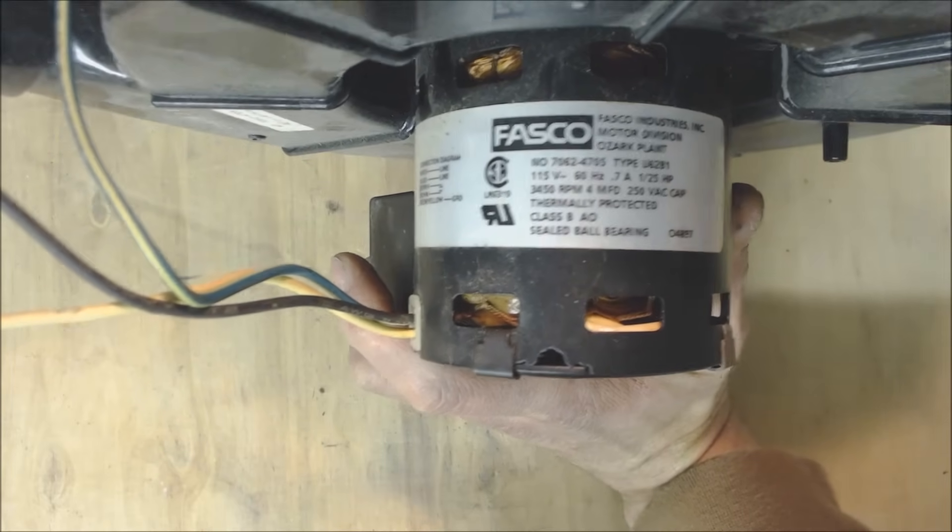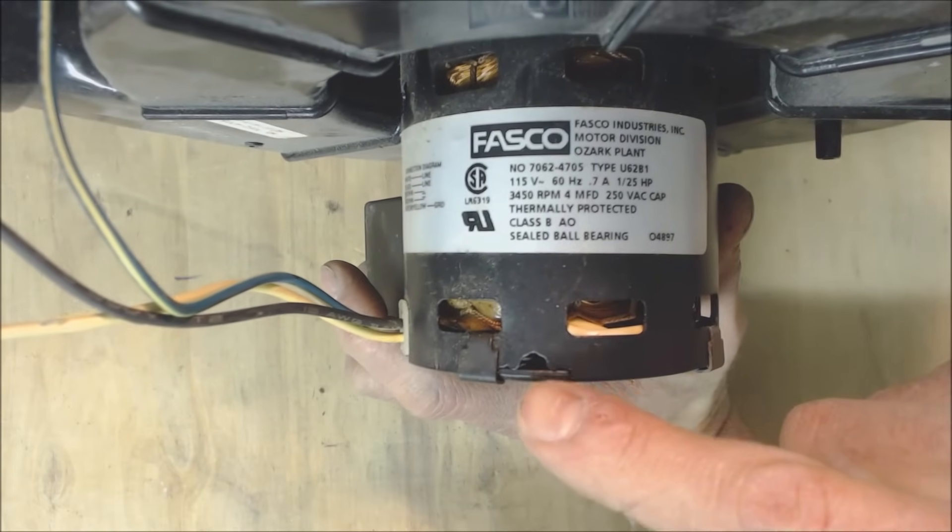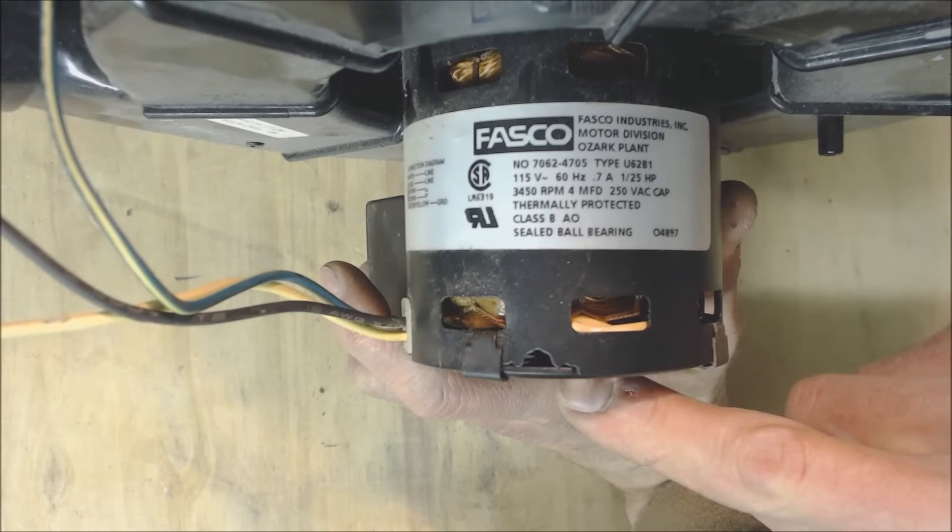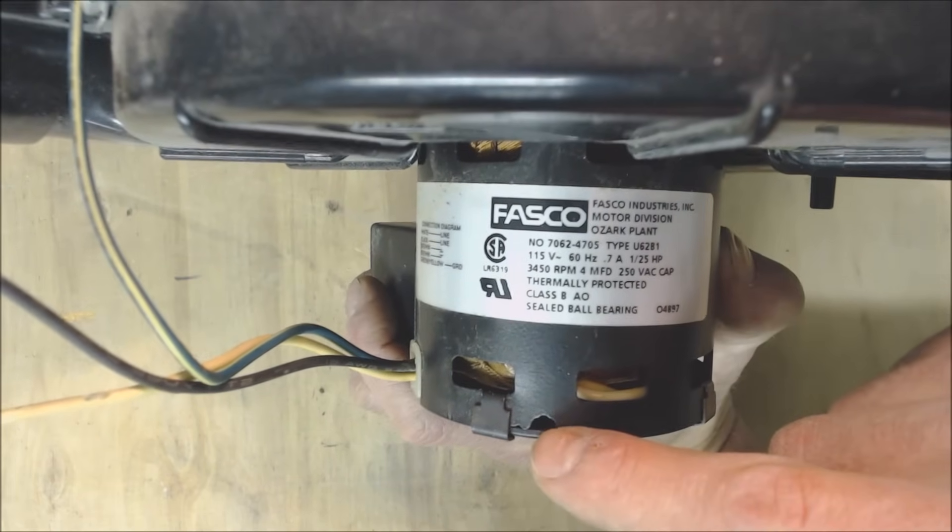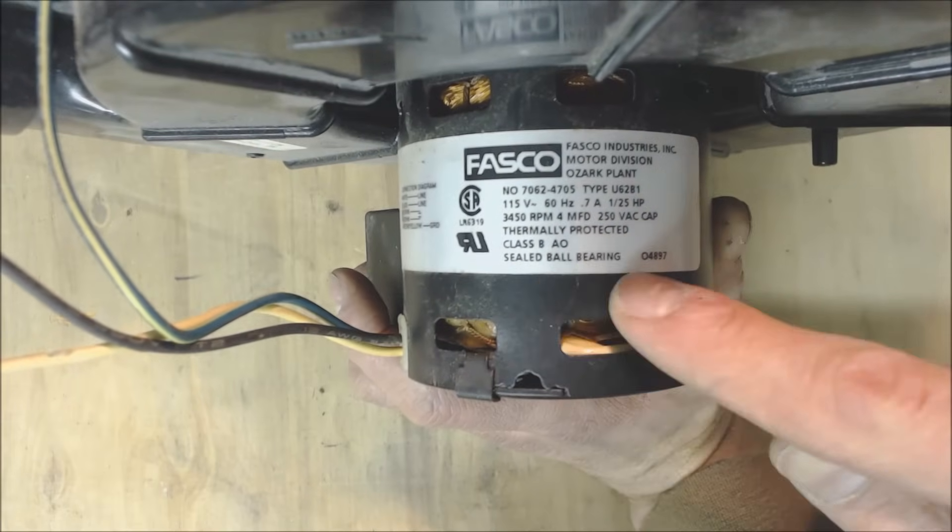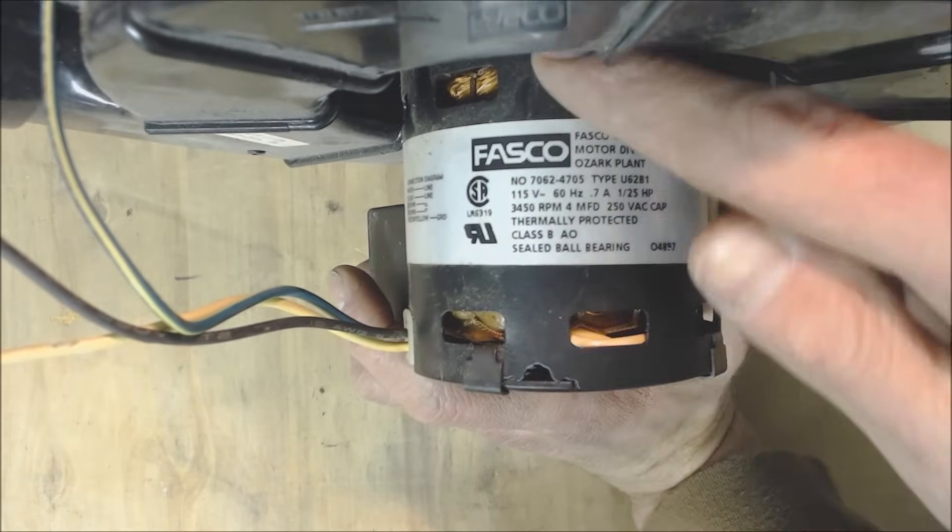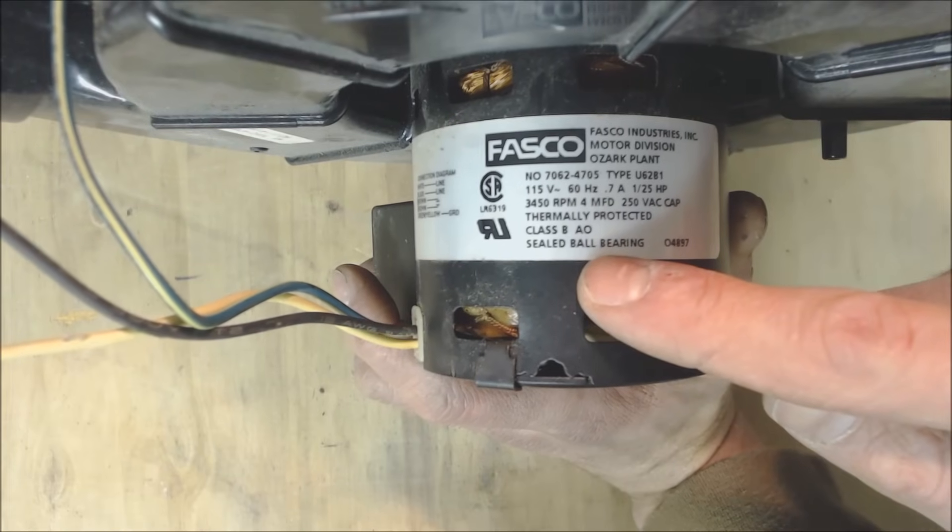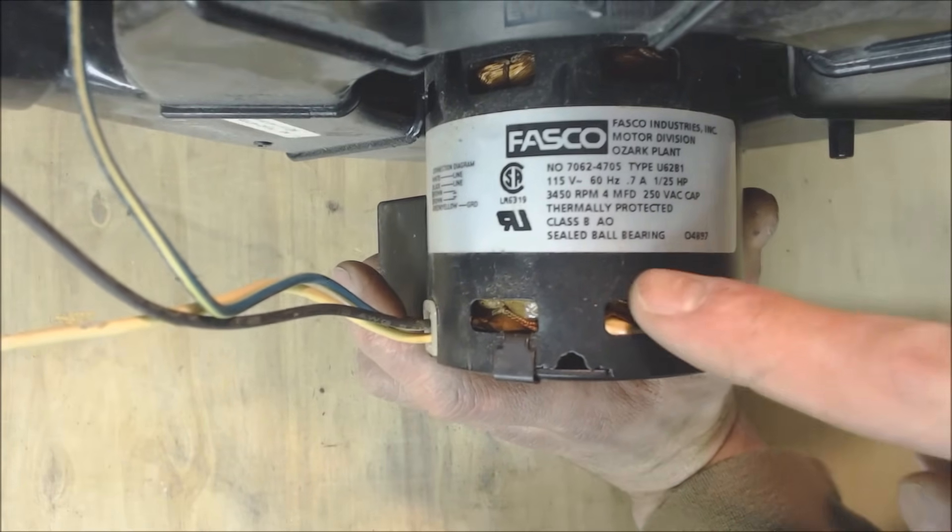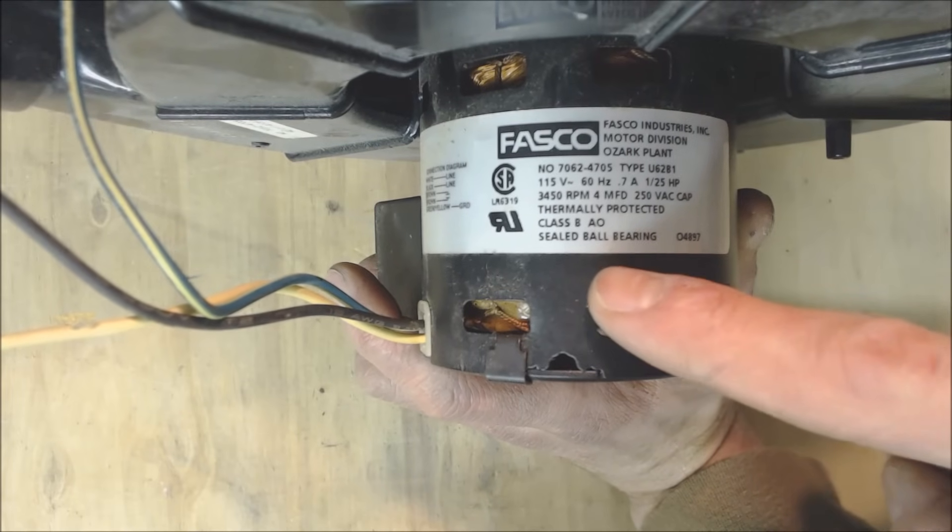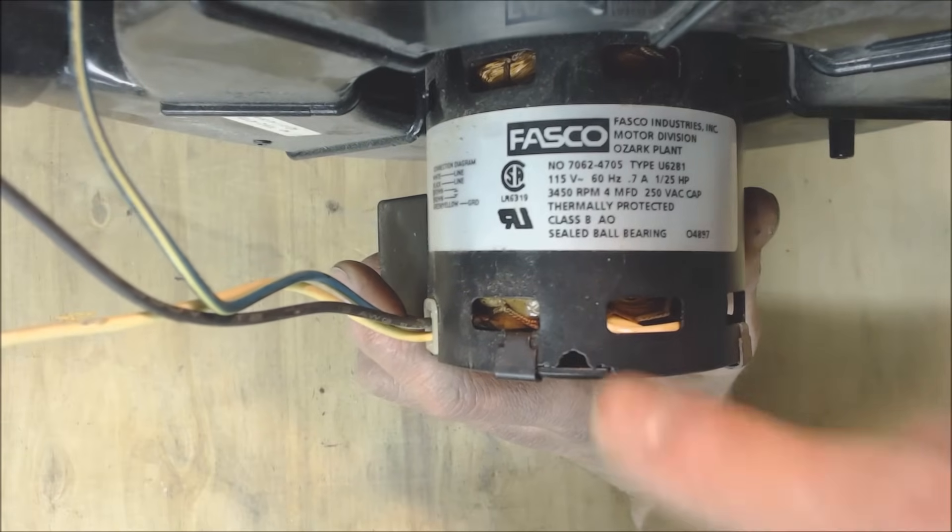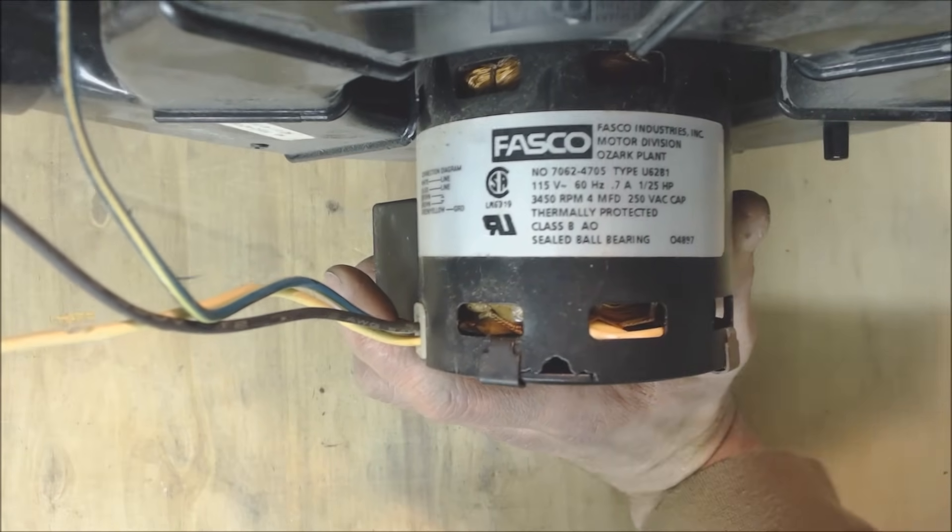Now just so you know, just because you see these ports right here does not mean that this is a non-sealed bearing that needs to be oiled. You can actually look inside and there is no trough for the oil and it actually says sealed ball bearings. So these outer casings of the inducer motor are made for a multitude of different model number blower motors. So this one happens to be one that has a sealed ball bearing and make sure that you do not put any oil down inside that hole for sure.